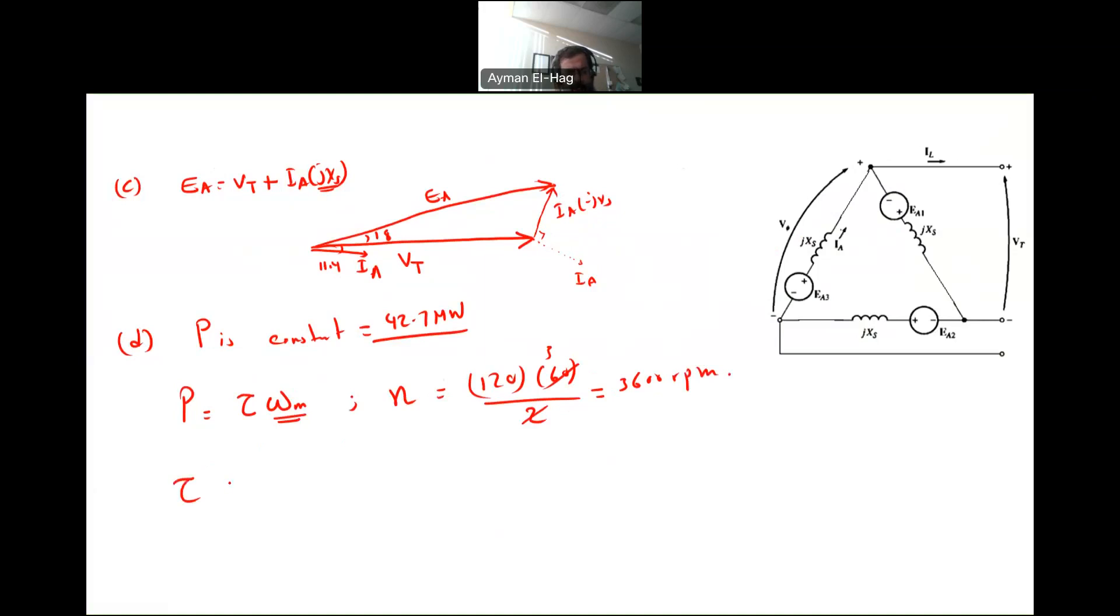So the torque will equal to the power, which is 42.7 megawatt, or times 10 to the power of 6, divided by the speed, 3600 times 2 pi over 60 to change the speed into omega. And this will give me a total torque equal to 113,300 Newton meter.